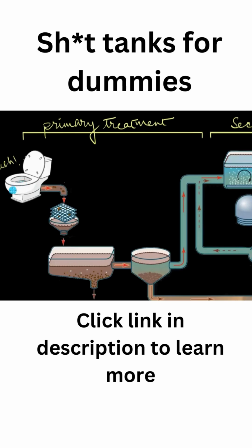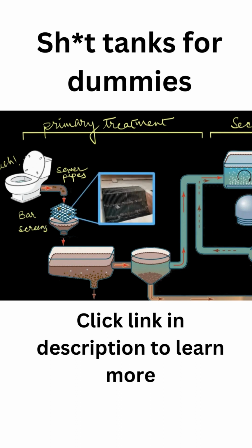When you flushed down last night's dinner, it got collected by the sewer pipes. These pipes are a part of an intricate network called the sewage system, which collects wastewater from all kinds of establishments. All of this collected wastewater or sewage passes through bar screens, which are these things right over here. Now, bar screens are these vertical bars which trap all the larger solid stuff like plastic, cans, bottles, wood, tissues, etc. We commonly call this step the pre-treatment step.